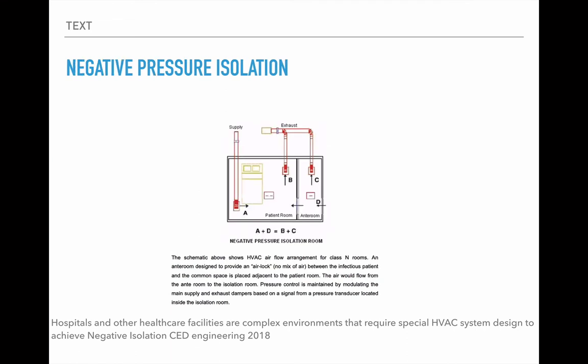In negative pressure isolation rooms, it's the opposite. You want air from within the room to only go out through the exhaust system and an HVAC microfilter designed to pick up microparticles down to nanometers. D, the door, should suck air in and not let air out. A and D, the flow from the door and the air supply, should equal the exhaust system, B and C, or B and C should even be slightly higher, to account for nonsensible losses and air leaks in these systems. This is just the basic difference between a positive and a negative pressure isolation room. In negative pressure rooms, you're protecting the rest of the hospital from the air inside that room.